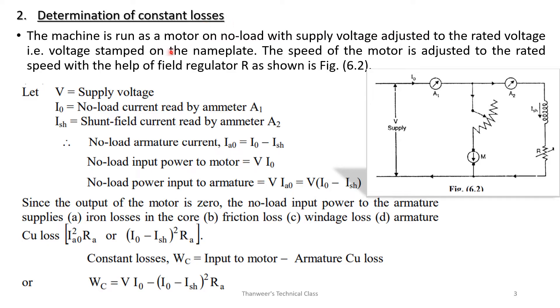For determination of constant losses, the machine is run as a motor on no load with the supply voltage adjusted to the rated voltage — that is, the voltage stamped on the nameplate. The speed of the motor is adjusted to the rated speed with the help of a field regulator R, as shown in Figure 6.2.